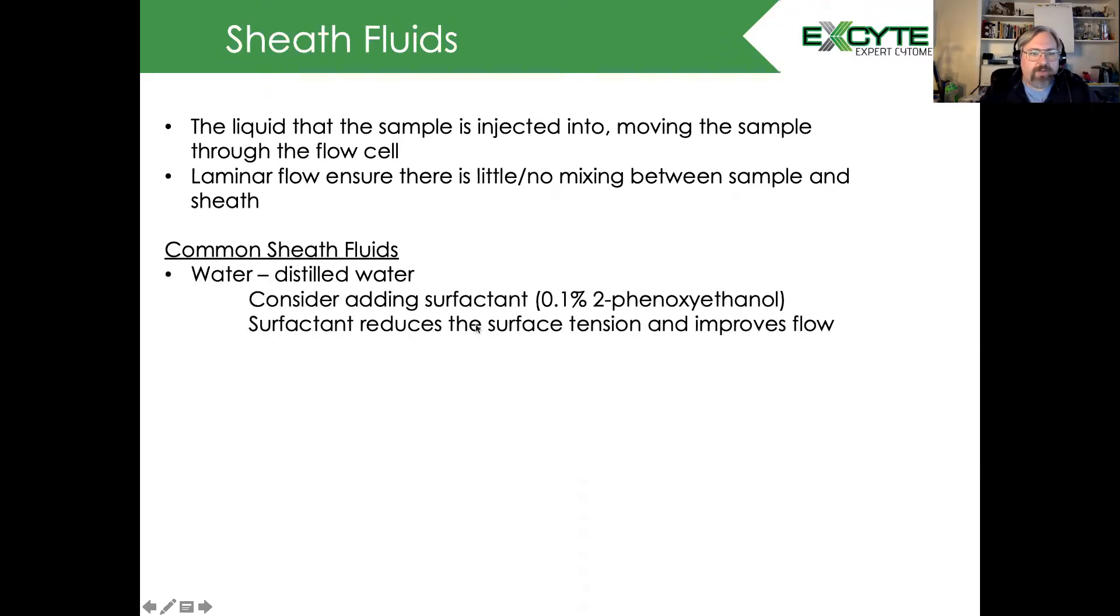A couple of common sheath fluids include water, just distilled water. I recommend adding a surfactant, something like 0.1% 2-phenoxyethanol. This helps reduce the surface tension and improves flow of the sample.